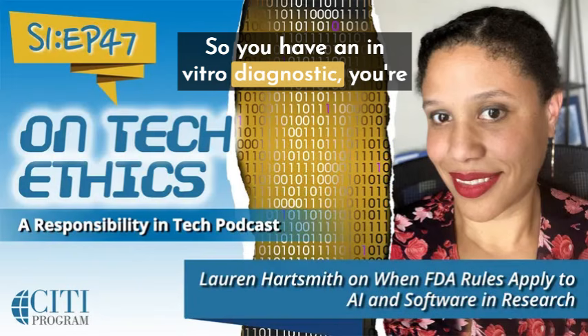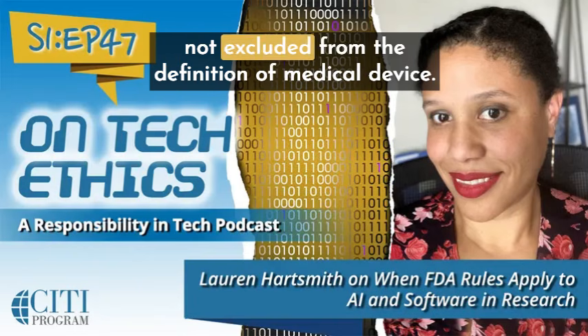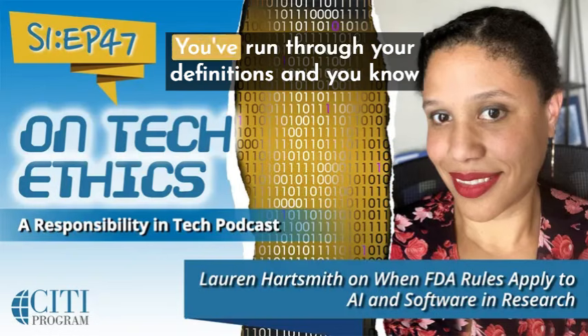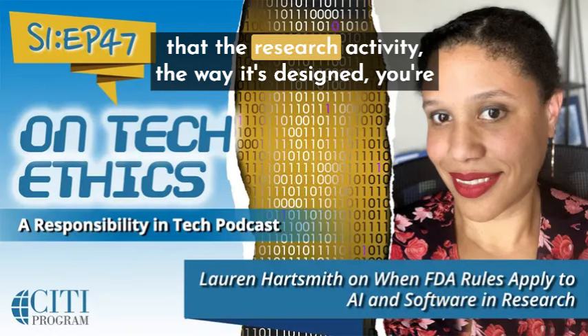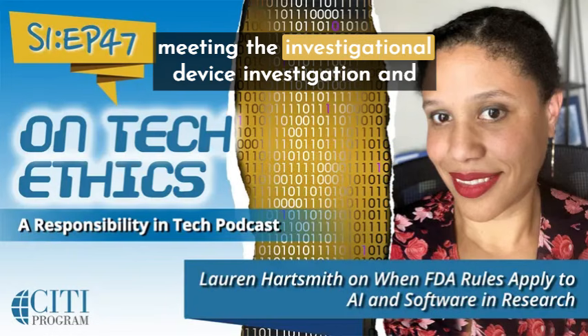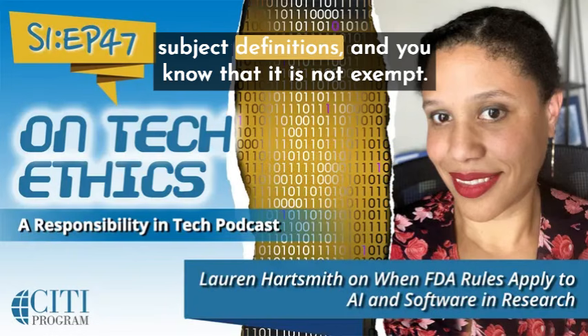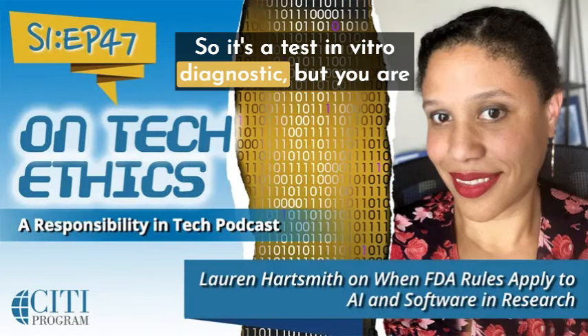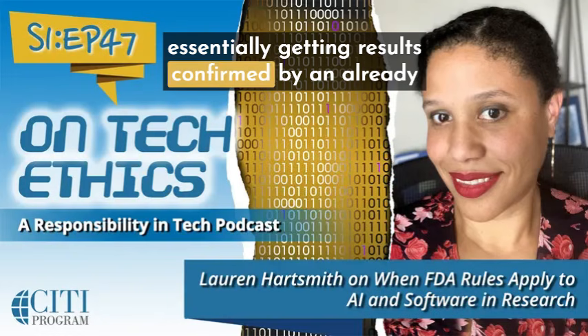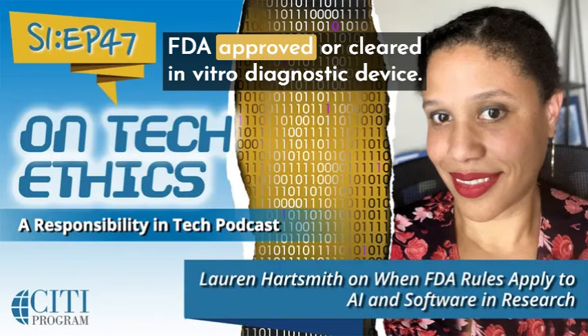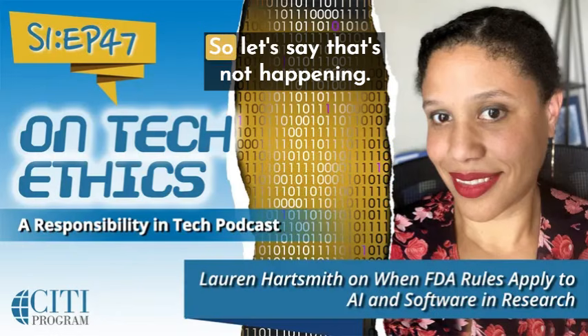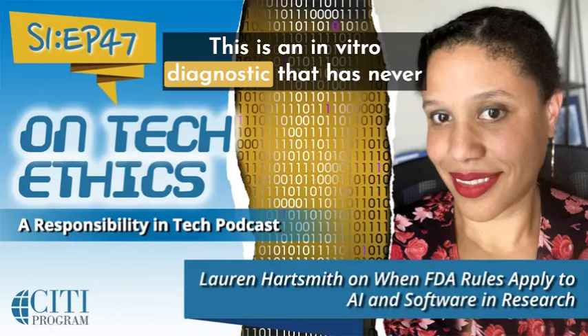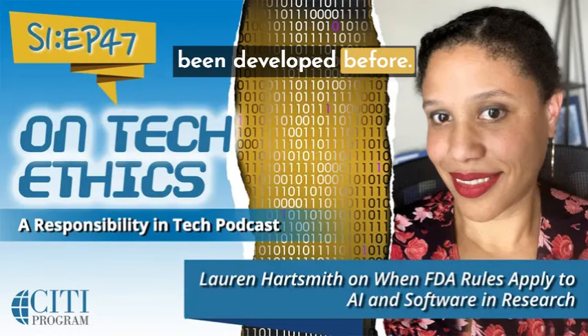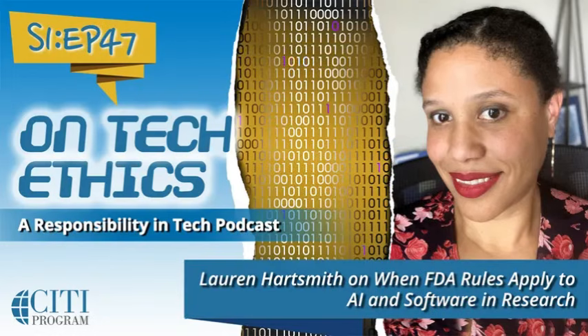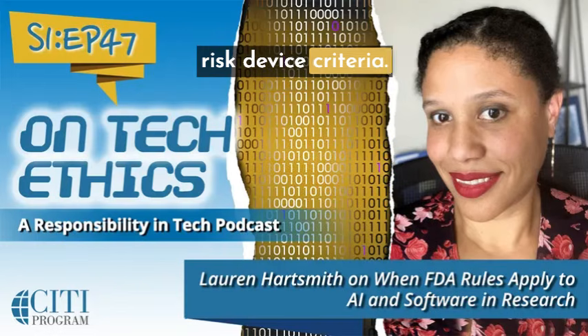So you have an in vitro diagnostic, you're positive it's a medical device, you know that it's not excluded from the definition of medical device, you know you've run through your definitions, and you know that the research activity, the way it's designed, you're meeting the investigational device, investigation, and subject definitions, and you know that it is not exempt, right? So it's a test in vitro diagnostic, but you are essentially getting results confirmed by an already FDA approved or cleared in vitro diagnostic device, right? So let's say that's not happening, right? This is an in vitro diagnostic that has never been developed before, right? So you're positive it's not under one of the exemptions. Okay, and then we get to the significant risk device criteria, right?